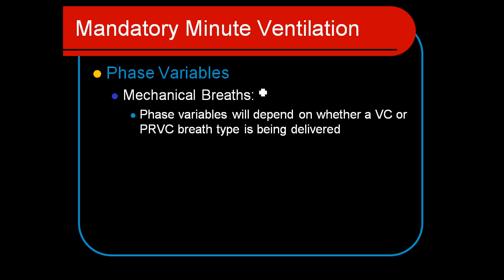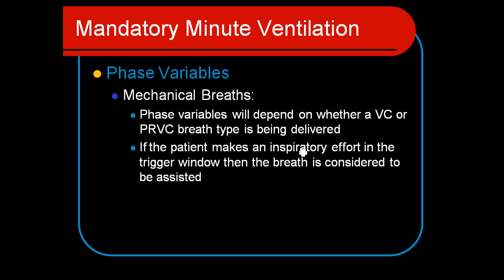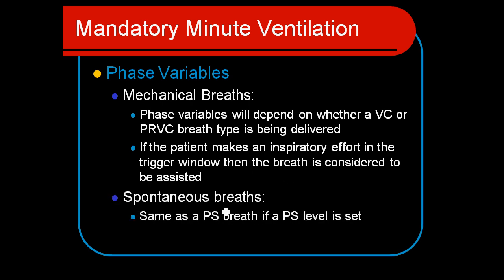The phase variables are complex because they depend on what's happening with each breath. They could be just like volume control, pressure-regulated volume control, or just like pressure support — it depends on what's going on with the patient. If the patient makes an inspiratory effort and triggers the breath, it could be assisted or entirely spontaneous. It's actually unusual for the mandatory minute ventilation requirement to kick in for most patients; usually the pressure support level is set correctly and the patient maintains their work of breathing without the MMV engaging.